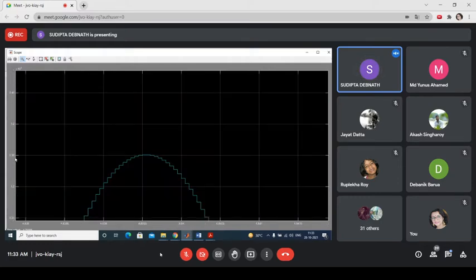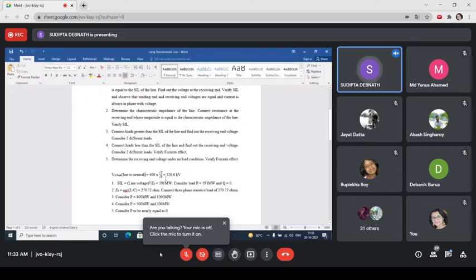It has increased to 3.35, that means 335 kV, 3.35 into 10 to the power 5. Please note down: at 500 megawatt load, the receiving end voltage is 335 kV. The sending end voltage is 326.6, and the receiving end voltage is now 335. So you can observe that the receiving end voltage has increased when the load is less than SIL.